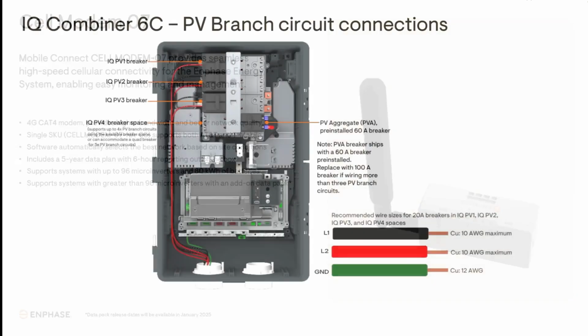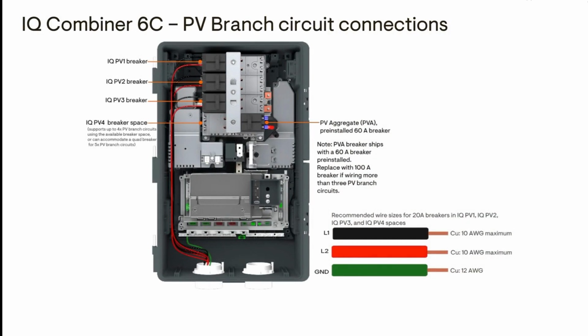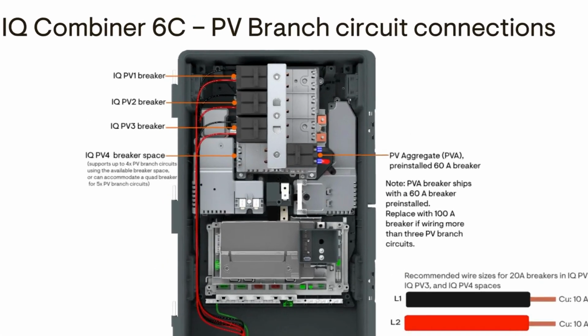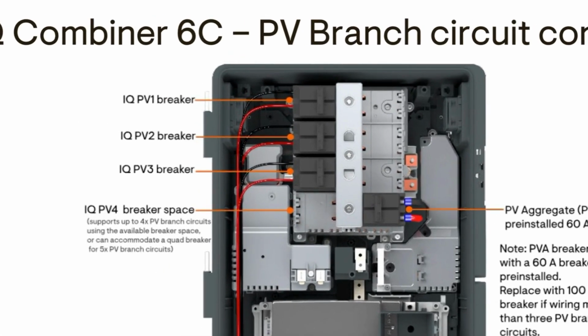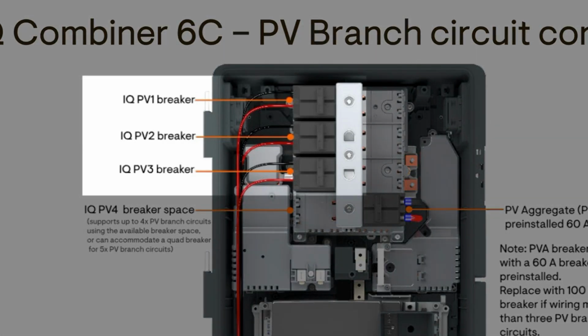Here is an overview of the layout of the Combiner 6C, showing its functional areas. On the top left we see Enphase PV branch circuit breakers. Located on the upper center part of the unit are the electrical buses for all of the breakers. PV breakers are located on the left side bus. Up to 5 Enphase IQ series microinverter branch circuits.